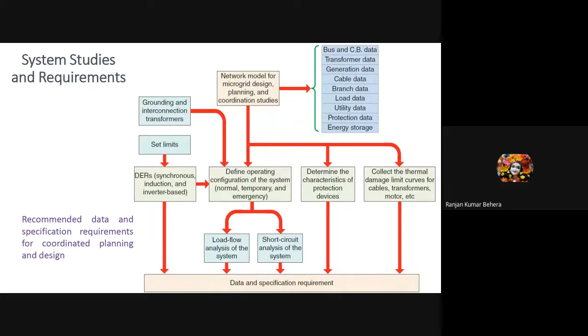For example, today our load is around 2.5, less than 2 MVA - less than 2 MVA load, but we put 2 and 2.5 MVA capacity. Why do we put 2.5 MVA? Because when this grows, it will require all these additional things.